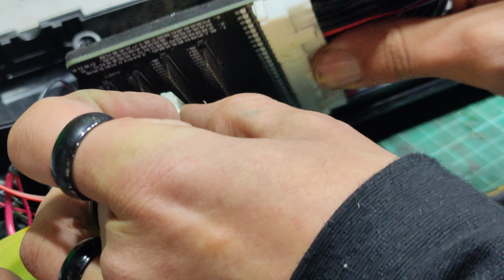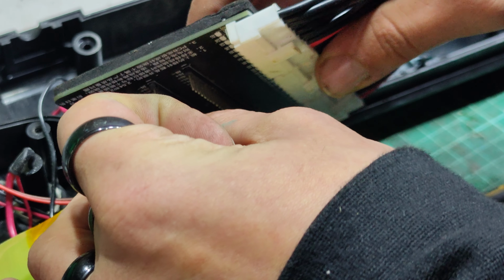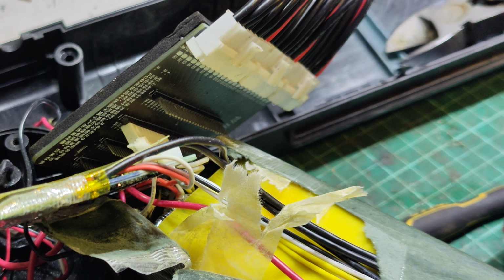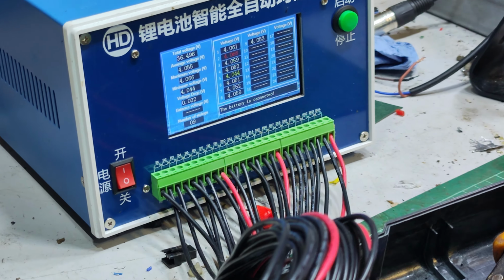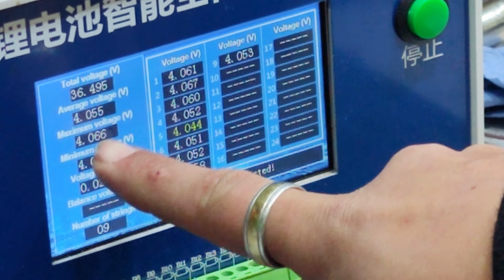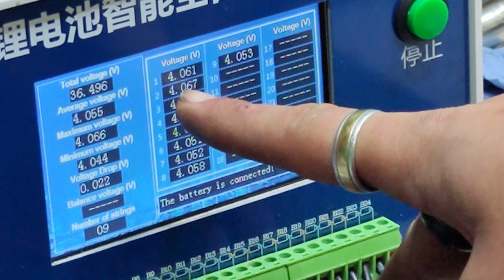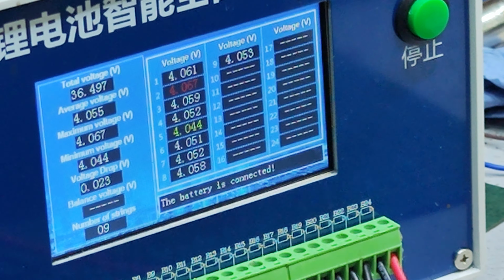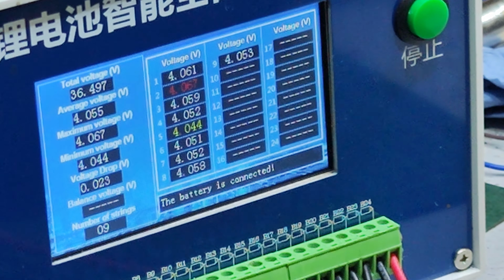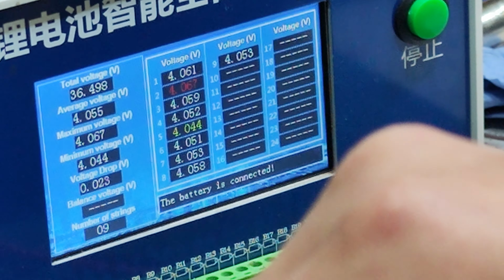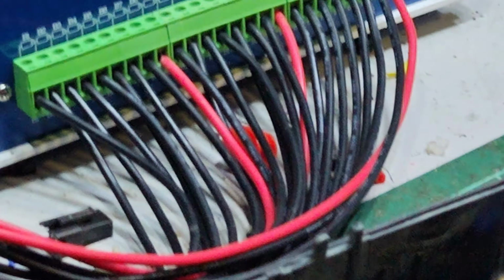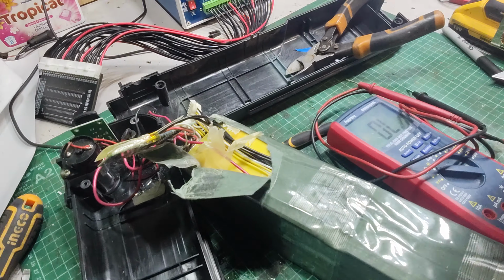Let's get the cells plugged into my tester and see what they're saying. And the cells are reading actually all good. See there, we've got average 4. The voltage drop's really not that big, but under load this was sagging right down to 3.1 volts. Oh, number of strings 9. We haven't got the positive on there. Let's just check what voltage that one was showing, shall we? Make sure that it's not some really low cell group.